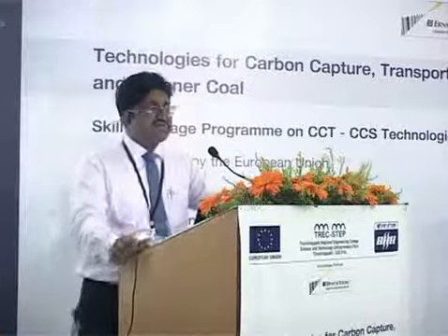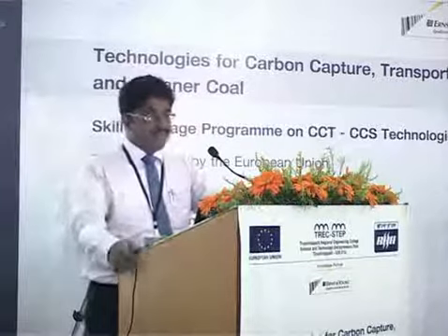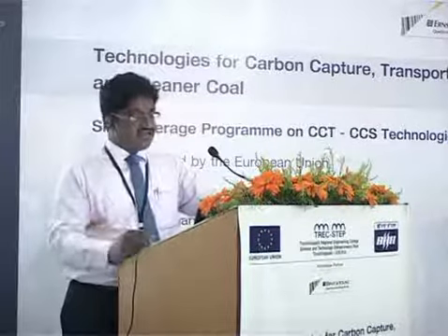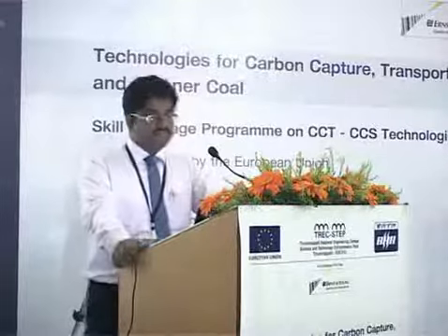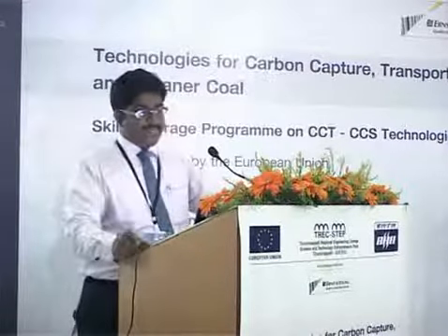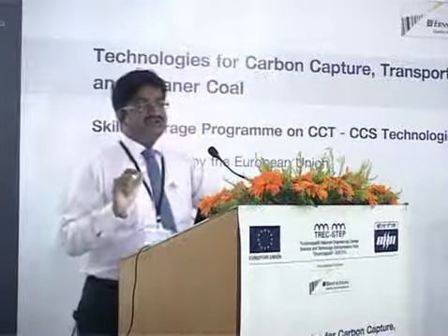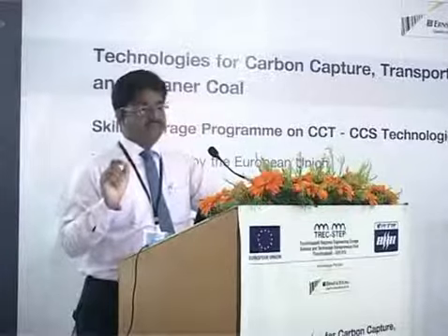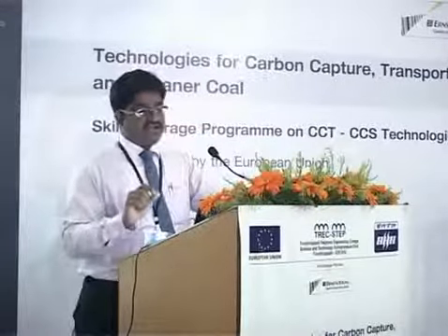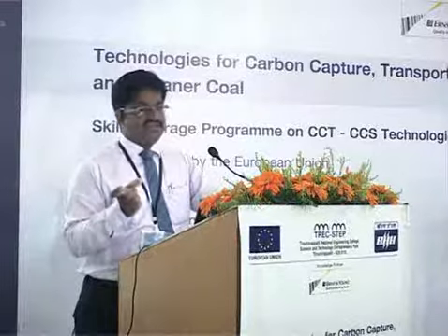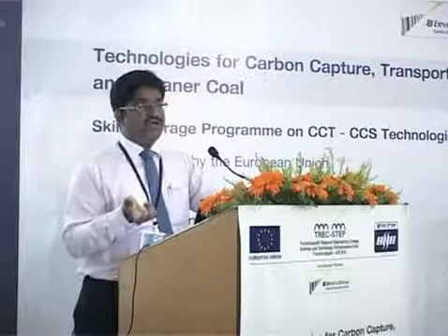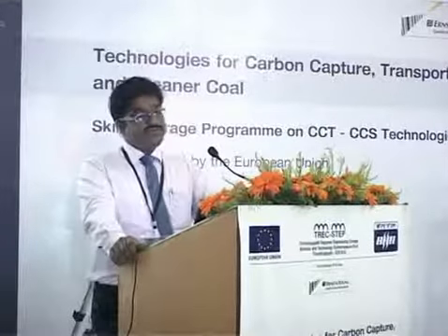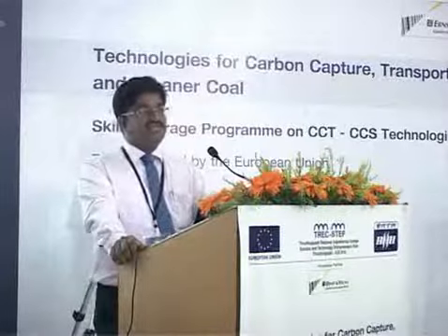So they want a capacity of 1320, it's available in both, and payload of 20%, quite possible. Auxiliary of 7.5%, yes. There's a discounting factor. GCV of 4 is the same, price is the same. But the parameter that you see, the project cost, is high, about 1,500 crores costlier than the subcritical power plant. But if you see the station heat rate, yes, they are getting an efficiency gain. So this is how this particular project can be considered for CDM.